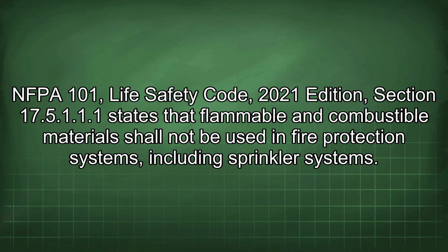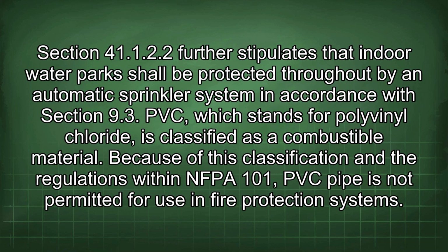NFPA 101 Life Safety Code 2021 edition, Section 17.5.1.1.1 states that flammable and combustible material shall not be used in fire protection systems, including sprinkler systems. Section 41.1.2.2 further stipulates that indoor water parks shall be protected throughout by an automatic sprinkler system in accordance with Section 9.3. PVC, which stands for polyvinyl chloride, is classified as a combustible material.